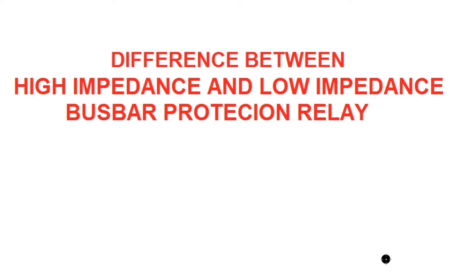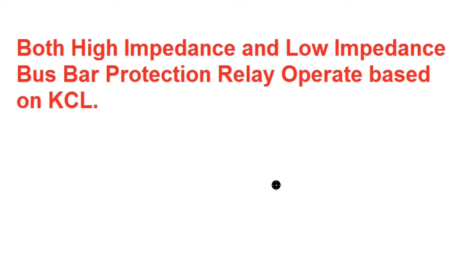Hello friends, today I will discuss the difference between high impedance and low impedance bus bar protection relay. Both the high impedance and low impedance bus bar protection relay operate based on KCL, that is Kirchhoff's current law. So current entering a node and leaving the node sums to zero. During normal condition, the summation of current entering and leaving for a particular bus will be zero.